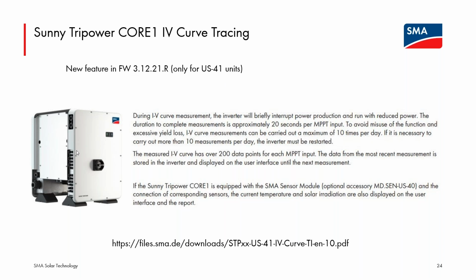This firmware has two major upgrades for the CORE1. The first one, and one I find very exciting, is the ability for anyone to trigger, in the user interface of the inverter, an IV curve tracing test. So log into the inverter. In the user interface, you can force the inverter to do an IV curve trace on its 6 tracking channel inputs. It takes about 20 seconds per channel, so that's roughly 2 minutes to do the test.